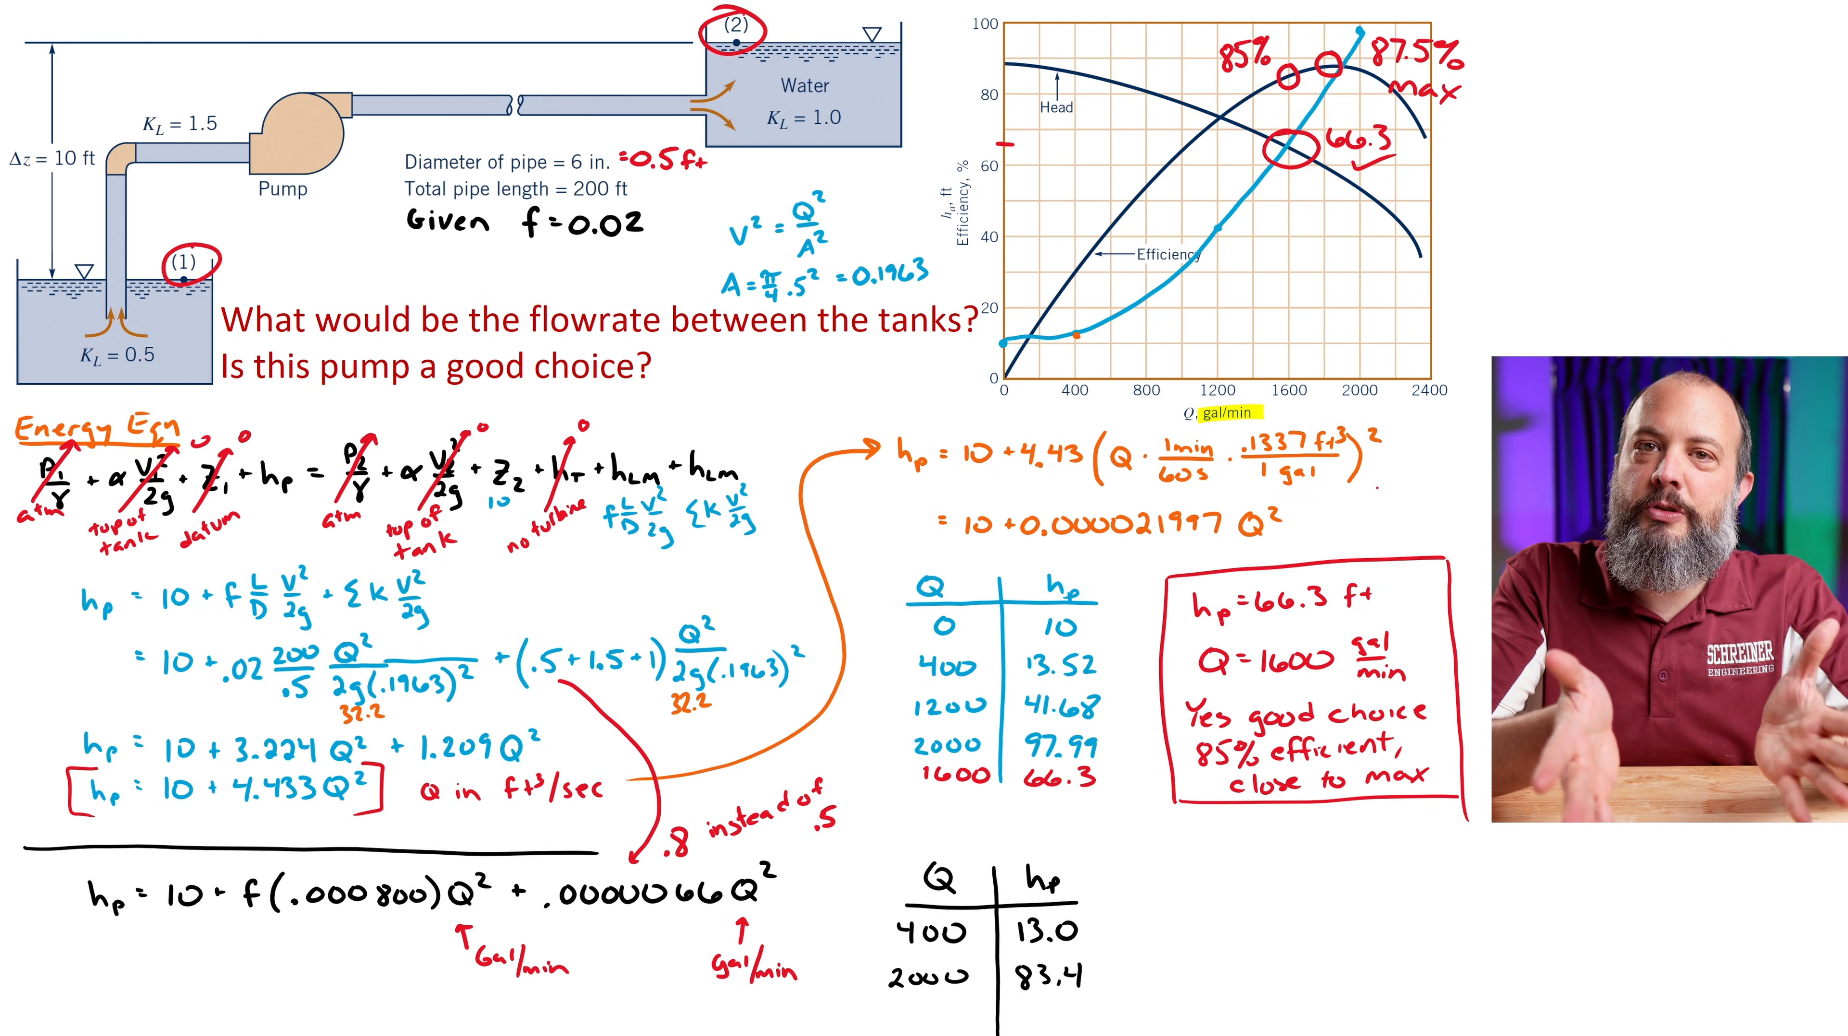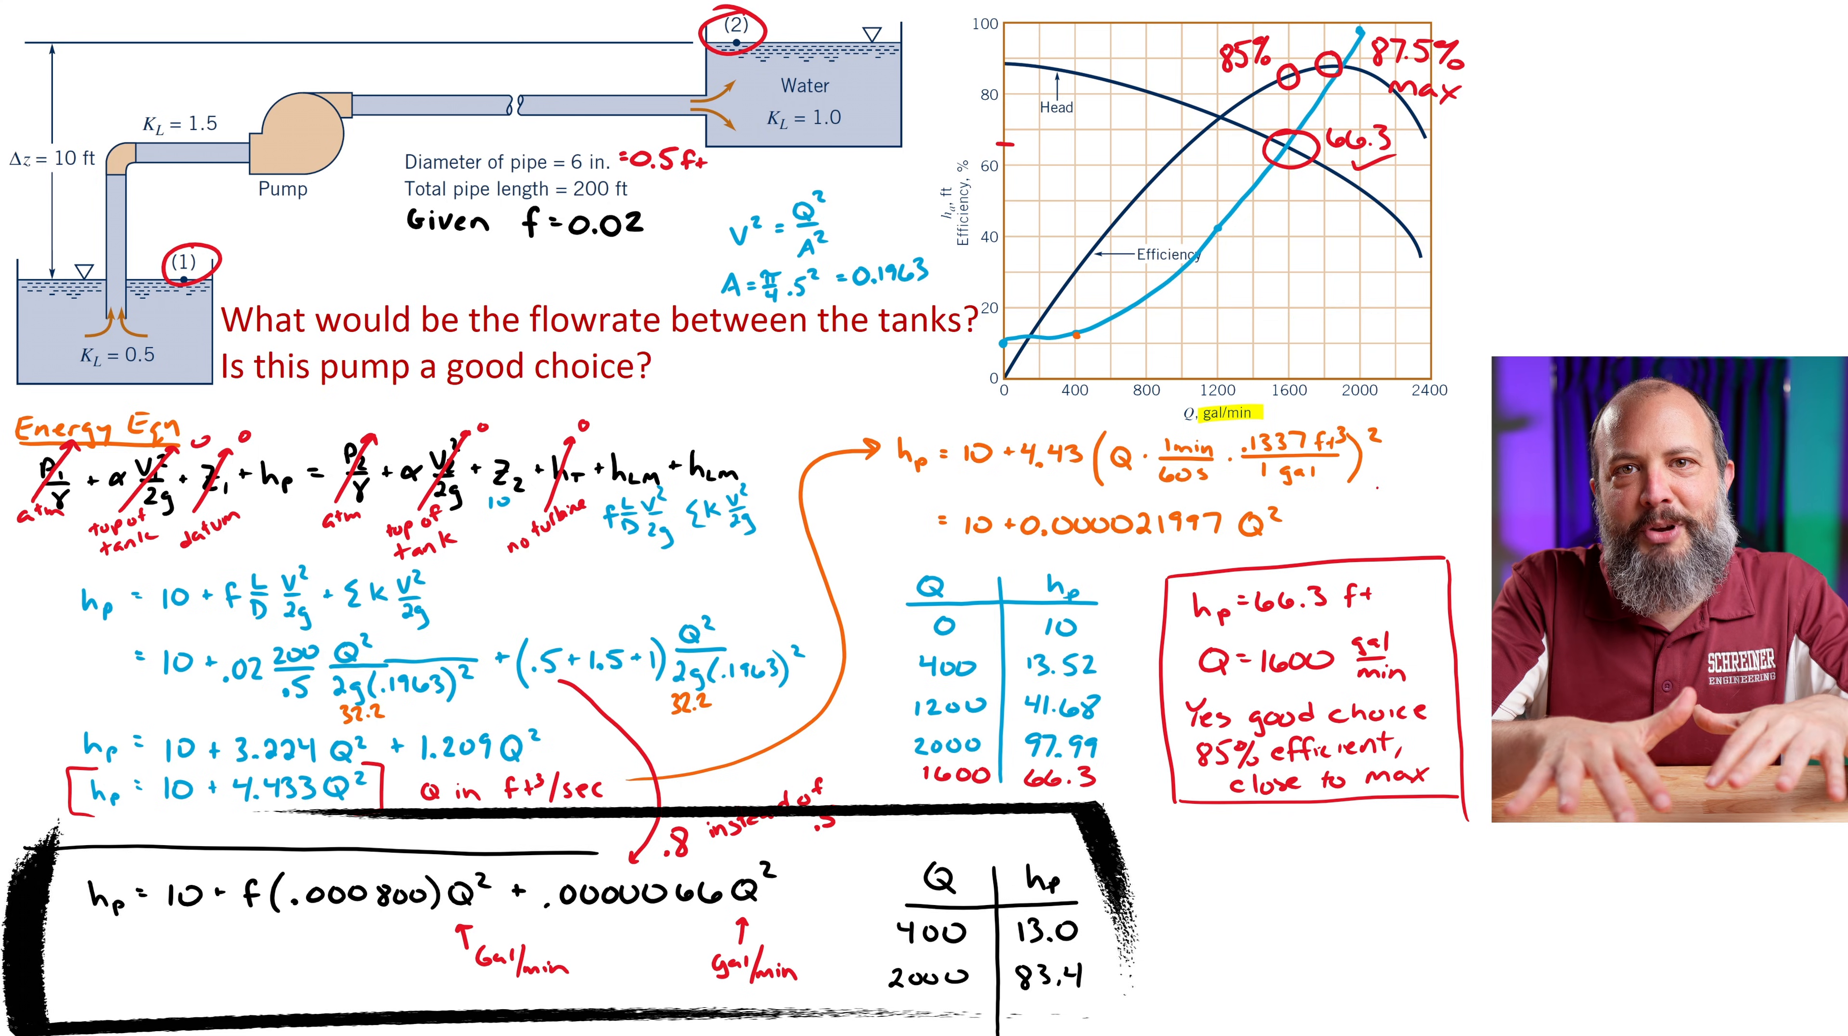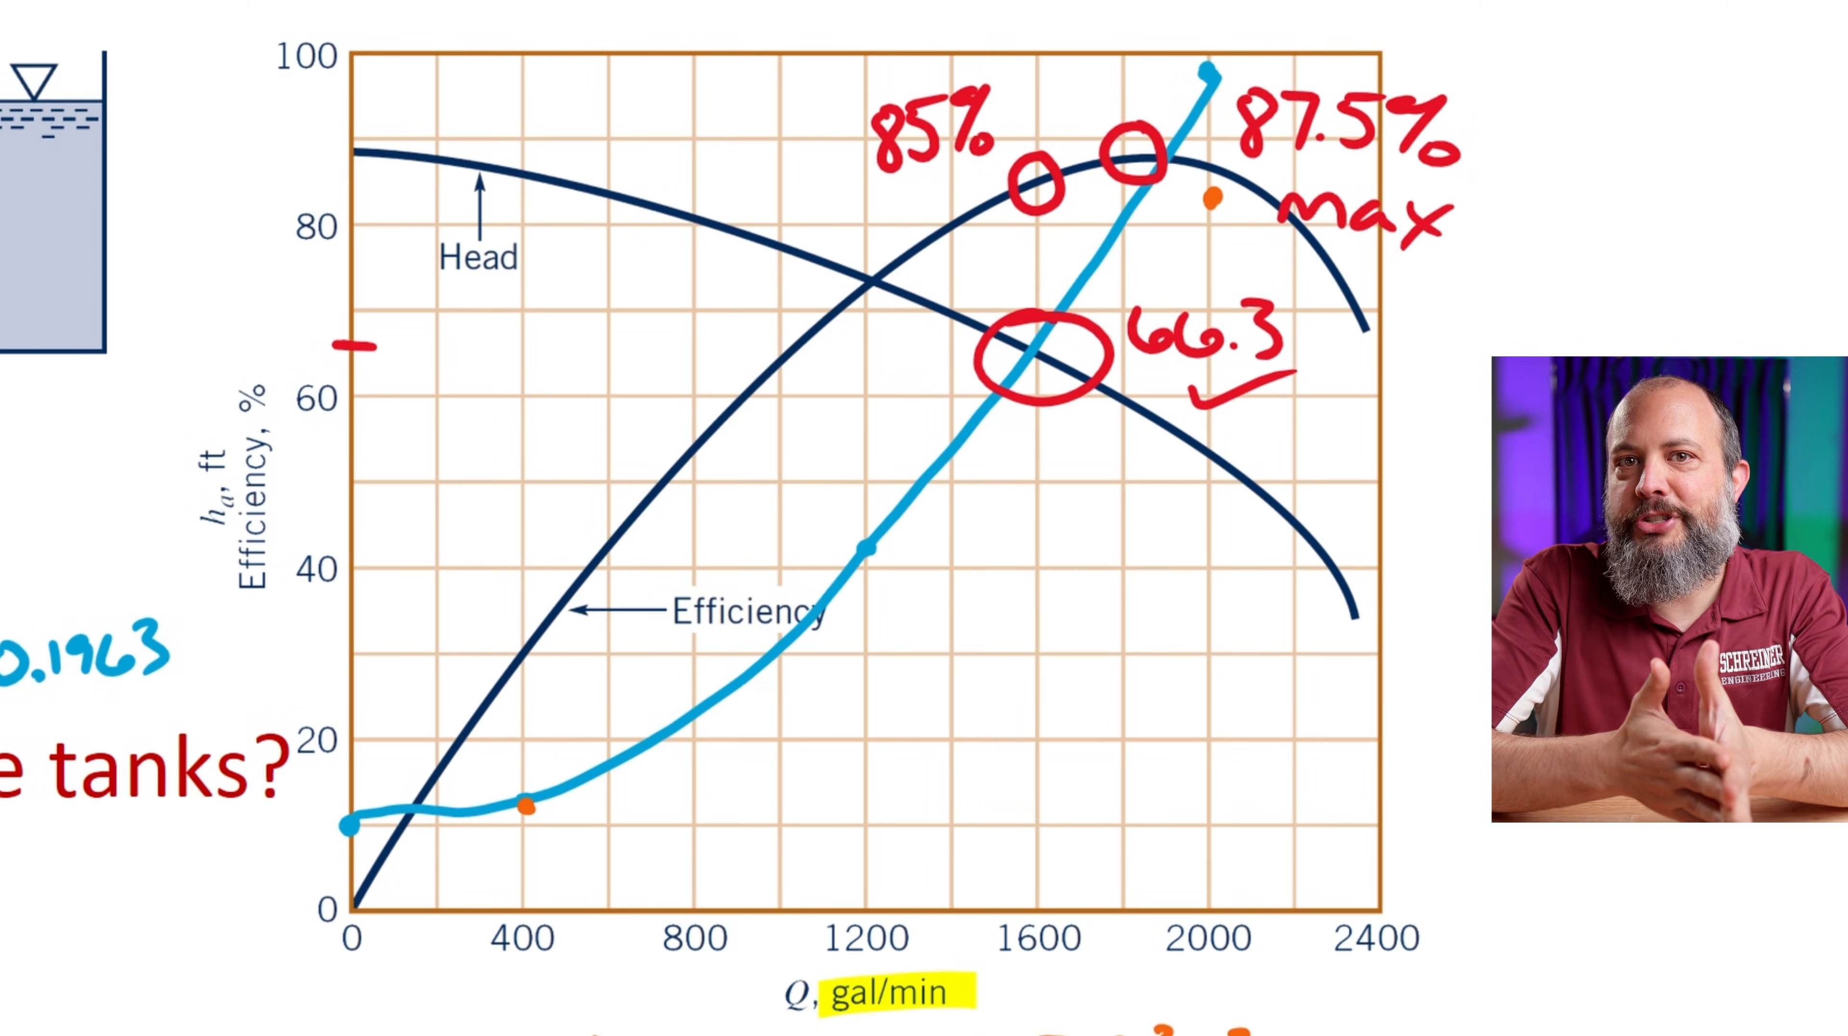The last minor loss source will be the exit, right? The sudden expansion into the tank. And since that's square edged, this table that I have in my book here shows that a minor loss K value of 1 does work for that. So if I do a whole bunch of calculator work with all of mostly the same numbers, but I have a different factor for F, and I'm also using a different factor of 0.8 for this minor loss at the re-entrant entrance, I get a slightly modified version of the pump head equation. For the value of Q at 400, I get 13 feet. And for the Q value of 2,000, where I solve the other friction coefficient, I get a value of around 83 feet.